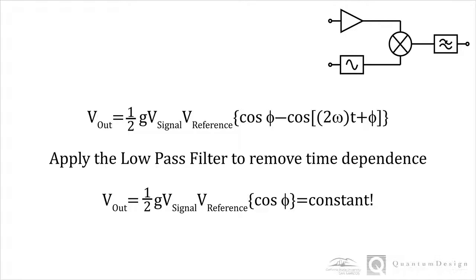The final output is therefore a constant value proportional to the product of the signal and reference amplitudes. In other words, the AC signal has been transformed into a constant DC output. This is why the technique is called lock-in amplification. The instrument is looking to lock in the signal input to the reference sine wave.